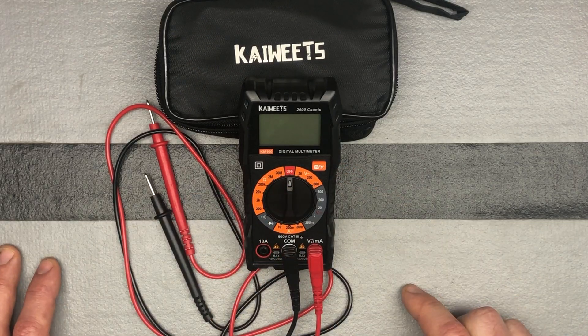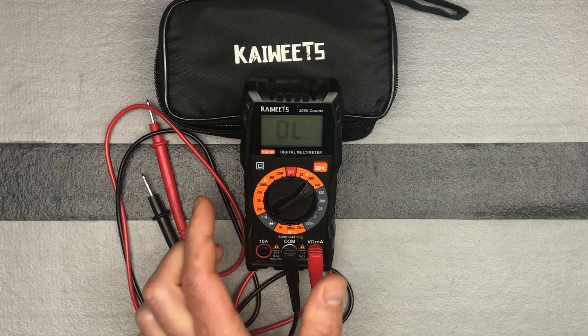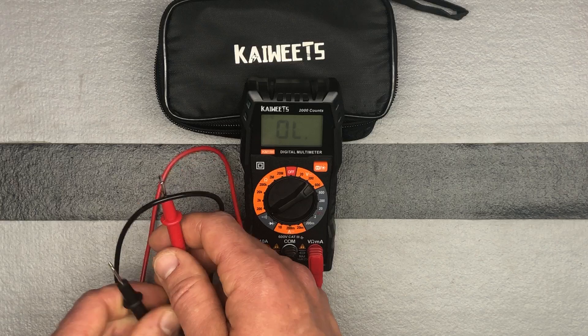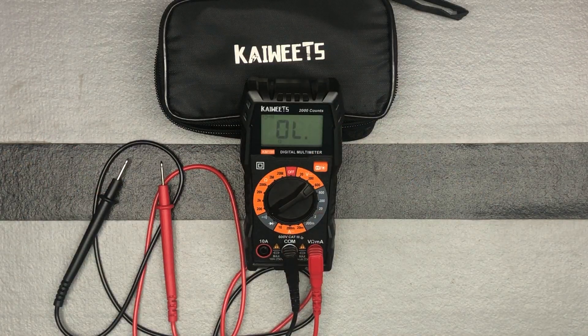If we want to do continuity measurement, de-energize the circuit you're going to be testing and turn the knob down to here. It's telling us we're out of the limit right now, but that's okay. Keep your probes in the same places. Touch the test lead tips together to check if they're connected normally — the buzzer should sound. You can hear that beeping, so yes, they're connected properly. Then go ahead and measure that circuit. If there is continuity, it will beep; if there is no continuity, OL will display.